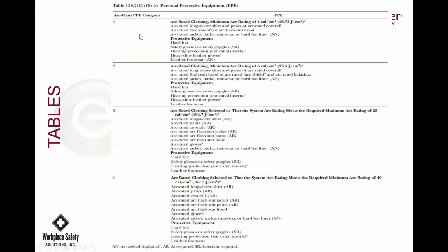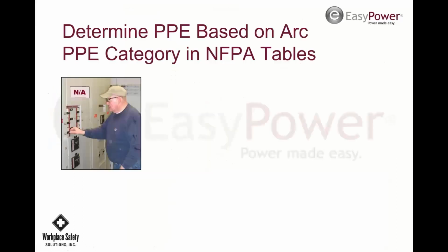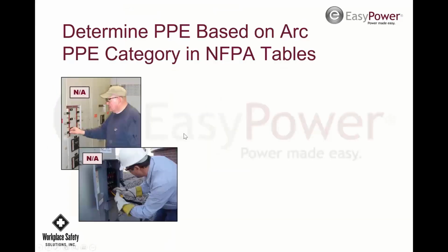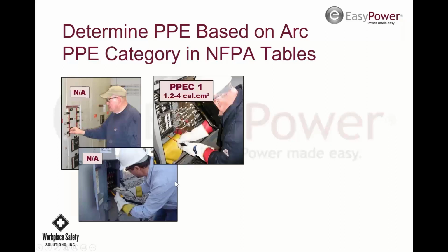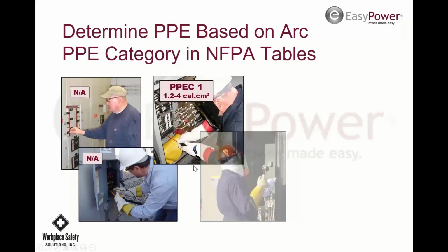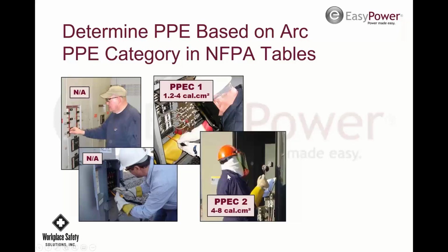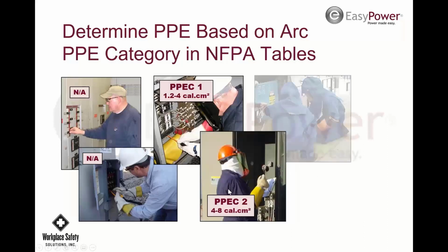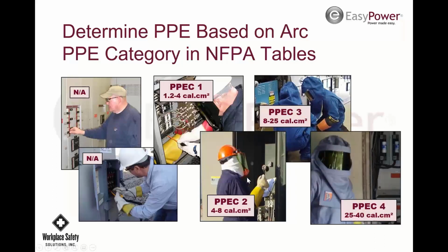Once you know the category rating of PPE, then you've got the 1, 2, 3, and 4, which tells you what you need to wear. This works fine as long as you're within the ranges. These used to be category 0. They're not applicable anymore. The reason this guy's got a hard hat and rubber gloves, of course, is the exposure to shock. Category 1 is 1.2 to 4. That's a shield. Category 2, 4 to 8. Category 3 and 4 is a suit. So once you're over 8, you're in a suit.